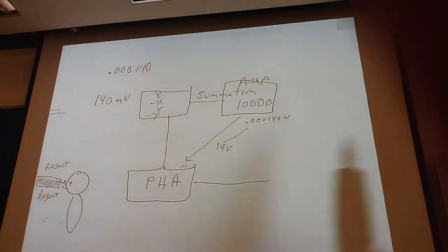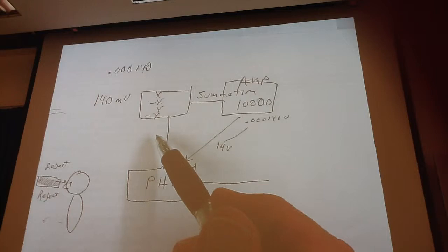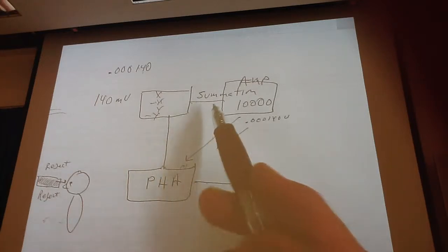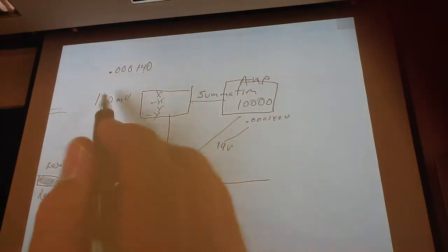So this is how we handle the problem when we change radionuclide settings. Let's pretend that we want to now image indium, so we change the collimator, and now I've got that coming in.